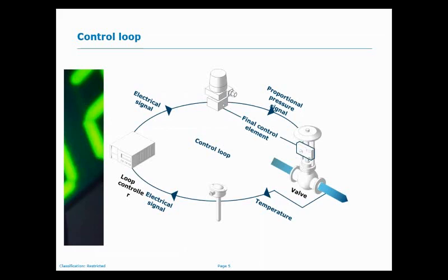This I2P converter is again an industrial standard device which should give the pressure signal for operating the valve in any standard industry. When you want to open or close a valve, what do you have to give? Just think of the tap that you open every day. What are you giving? You are giving a turning force, right? That turning force will be given by this electrical signal. If it's going to come as 4 to 20 milliamps, it will come through an analog output. This analog output, for example, will be calibrated from 0 to 100%.